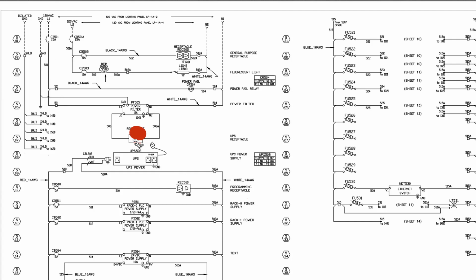UPSs are the same as you would use at home. A lot of people will plug their TVs and computers into UPSs. If you have a power failure, it'll keep them powered on. This is the same idea. So it's very good practice for PLCs to keep them on, even if power's off. Yes, for most facilities, if the power's off, you're not going to be able to run any pumps. You're not going to be able to open and close valves because there won't be power to those devices. But turning PLCs off and on, although they're normally fine, there's always a risk that they're not. So good electrical panel design is to include UPSs.